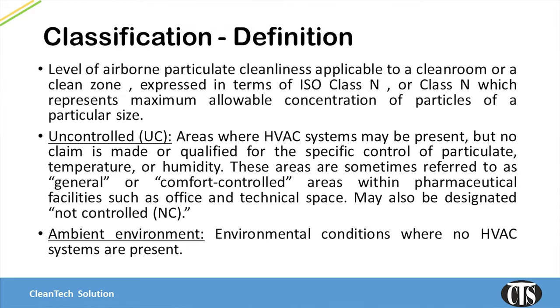How do we categorize cleanliness level? Various organizations have used different nomenclature to describe the level of particulate contamination, that is, the level of cleanliness. ISO names the categories as ISO 5, 6, etc. USP and USFDA refer to it as Class 100, Class 10,000, etc. WHO and EU classify it as Grade A, Grade B, etc. CDSCO categorizes it as Class A, Class B, etc.